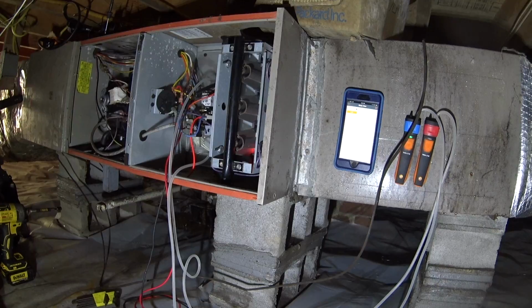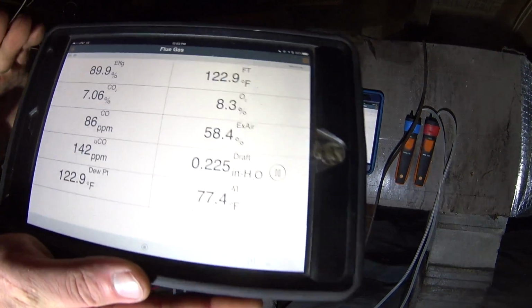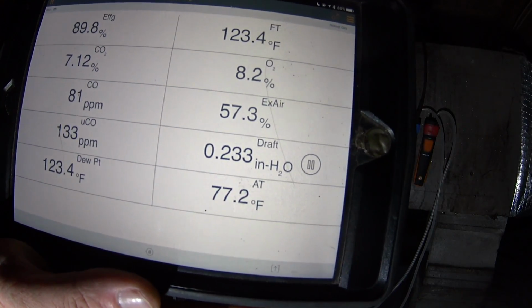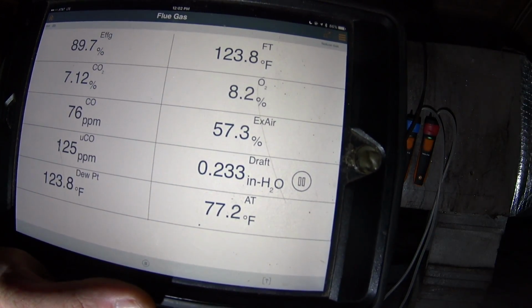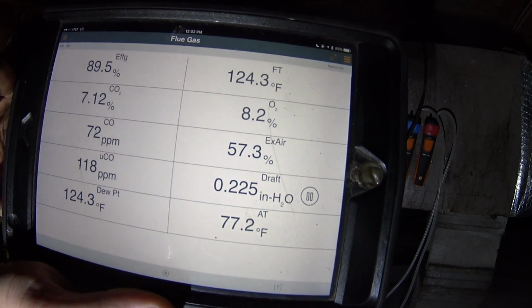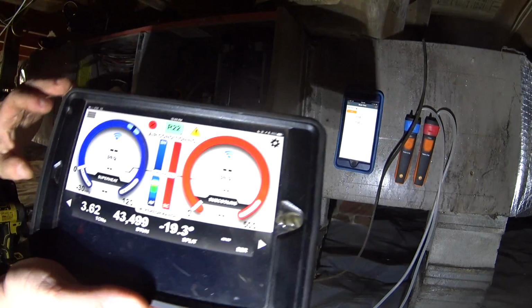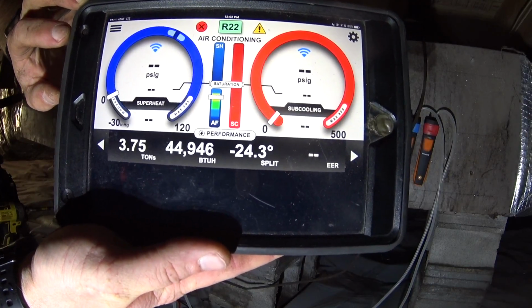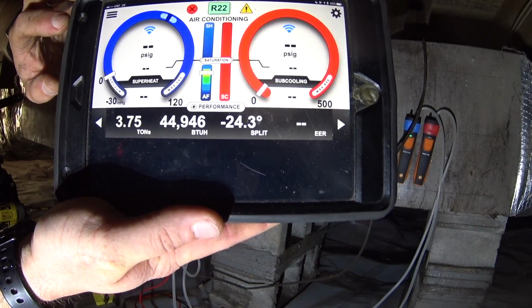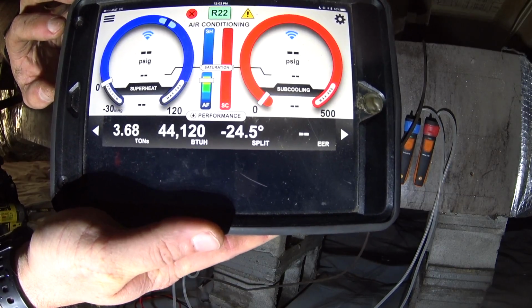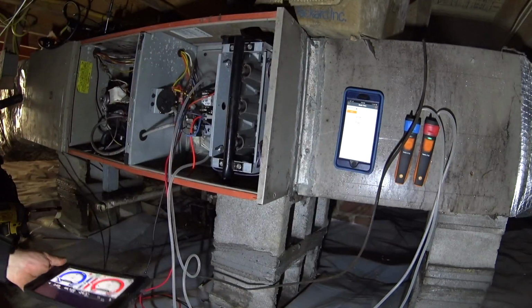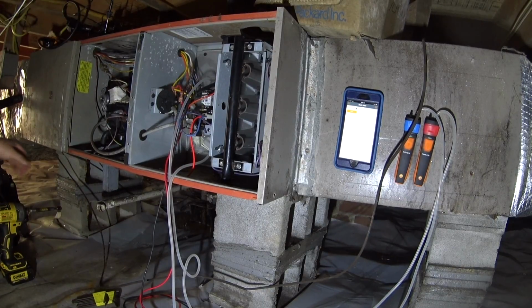All right, second stage is running 3.6. We're going to give it a few minutes to balance out before we attempt to clock the meter. Excess air is looking a whole heck of a lot better at 58, 57%. We're between 6 and 9 on CO2 and O2. We were at 19 degrees on first stage, and we're coming up 24. We're going to let it run for a while and balance out before we worry too much about it.